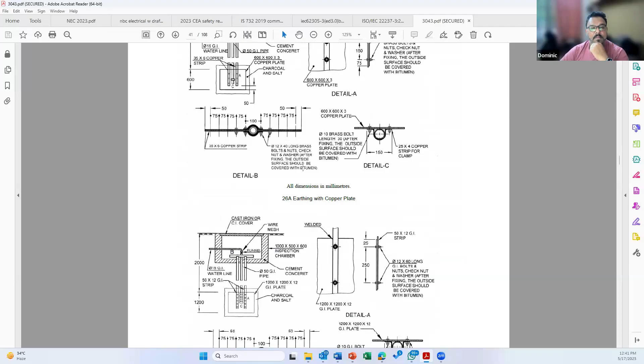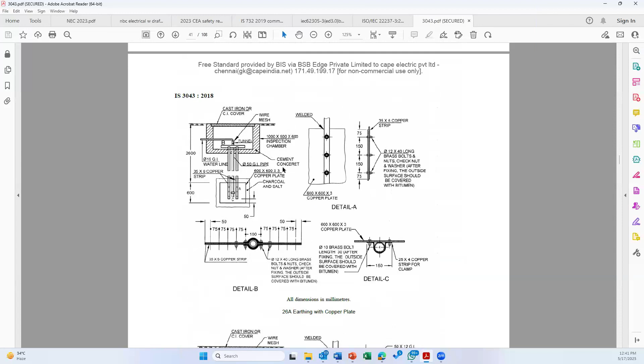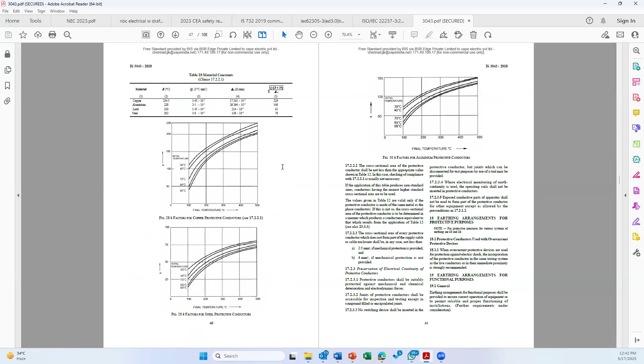But the basic question is, for the plate earth electrode, the standard is talking about not putting an earth pit. The picture is just to give an idea that you can make an earth pit, if required, as per this figure. It doesn't mean that you must make hundreds of earth pits all around your building and factory and put everything into the earth pit; that is wrong. I fully agree with that statement. How to make the pit and how many are required, we understand. But total elimination of the earth pit is not possible, that's what I feel. No, whether it is possible or not is up to you.